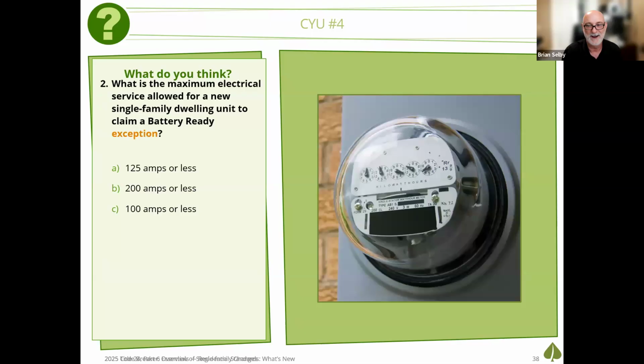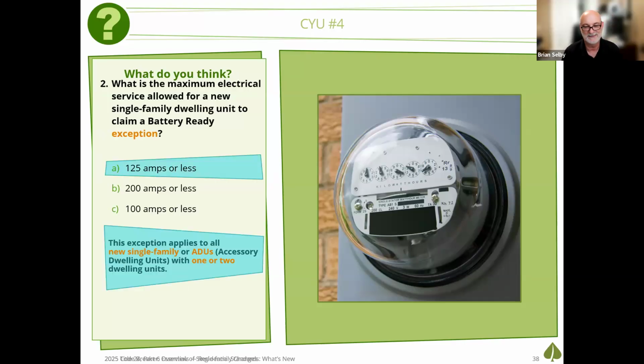So. All right, what do you think on this one? What is the maximum electrical service allowed for a new construction single family dwelling unit to claim a battery ready exception? Right? Talking about this service panel or meter, right? If we want to meet an exception under the code, is that 125 amps or less, 200 amps or less, or 100 amps or less? I think everybody is on board with, yeah, A is the correct answer there. That was a new exception if that service meter is rated for less than 125 amps or less.